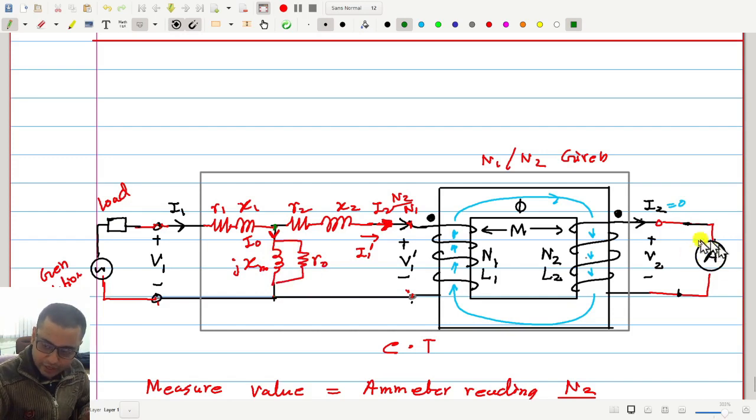In another case you are dividing by the meter impedance Zm. Now both these currents will be in the same direction if this impedance and this impedance have the same angle. Then I naught and I2 will be in the same direction, and there will be no angle difference between I naught and I2. Therefore this angle and this angle should be the same. Once again, there is a concept of angle matching. If you use a prescribed meter with a prescribed power factor angle, your error will be minimum.